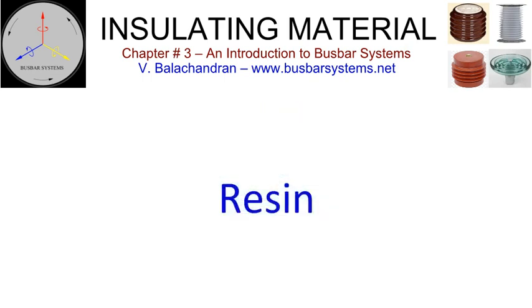Resin. Porcelain insulators have to be manufactured in bulk for a commercially viable price and require a long lead time dictated by the process. With porcelain insulators and bushings getting expensive and requiring longer lead time, they began to get substituted gradually by synthetic resin insulators and bushings. Due to their low cost, light weight, better lead time, and acceptable mechanical and electrical properties, several manufacturers of busbar systems have opted for insulators and bushings manufactured with synthetic resins. Synthetic resins can be formulated and synthesized to deliver the desired performance for a given application.